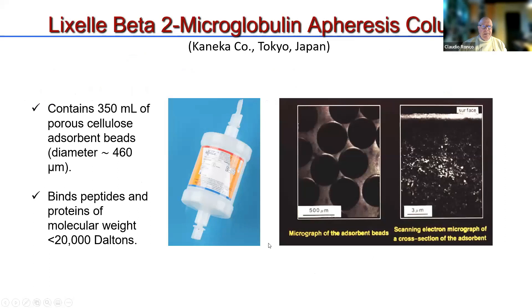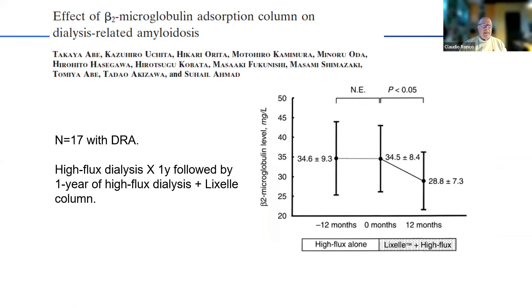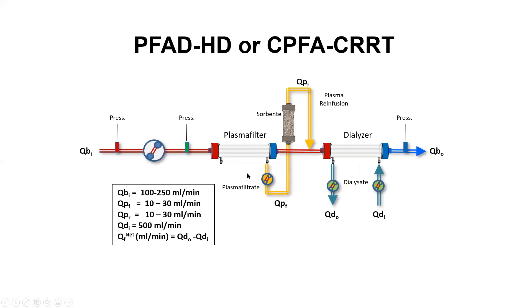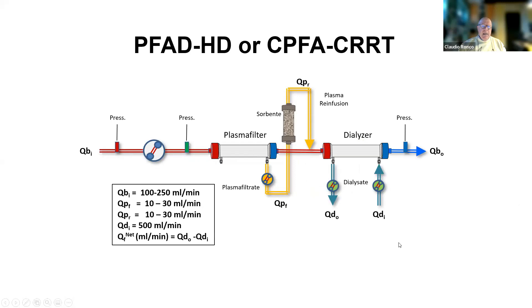There are other adsorbents that have been utilized, like the Lixelle from Kaneka, mostly for beta-2-microglobulin. It has been shown to have a significant effect on beta-2-microglobulin over time when using Lixelle plus hemodialysis. You can also utilize plasma separation and pass plasma through the sorbent instead of blood, allowing the use of specific sorbents for different purposes such as bilirubin or other molecules not removed by direct hemoperfusion. This can also be combined with CRRT, as done for example with CPFA.